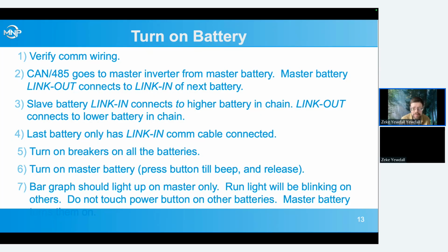You want to turn on the breakers for all the batteries. And then you turn on the master battery. You press the button for about 3 seconds and release it. And the bar graph will light up only on the master battery. The run light will be blinking on all the others, but there's no bar graph on them, and you don't want to touch any of the other power buttons. If you touch the other power buttons, you'll actually be turning them back off. So the master battery, when you turn it on, it'll turn all the rest on, and seeing the run light on the rest of them, but not the bar graphs on, lets you know that it's properly stacked and the battery's working.